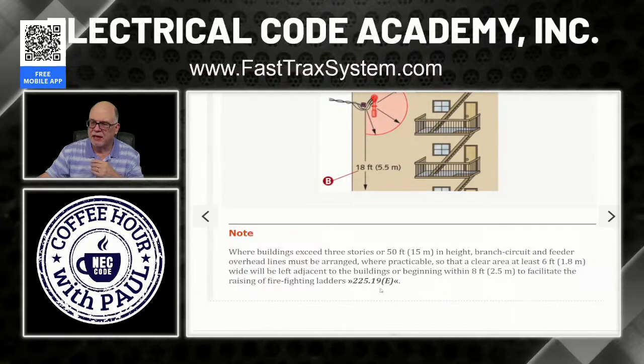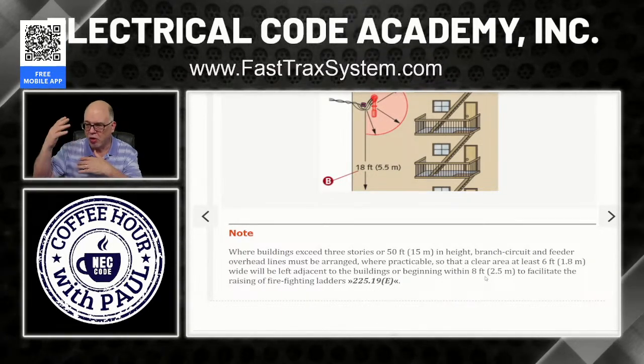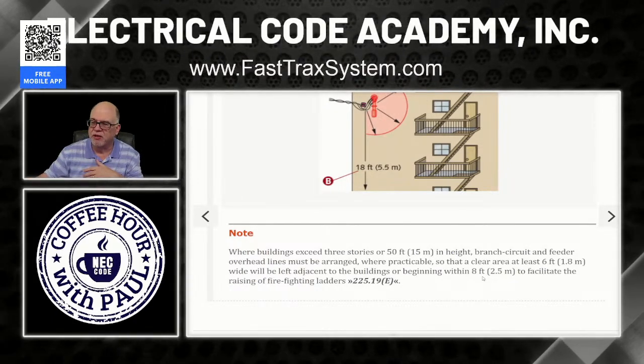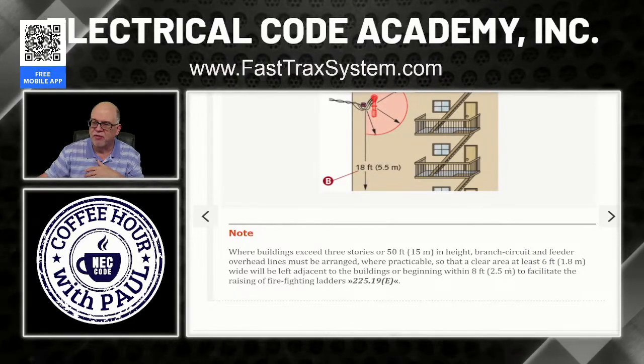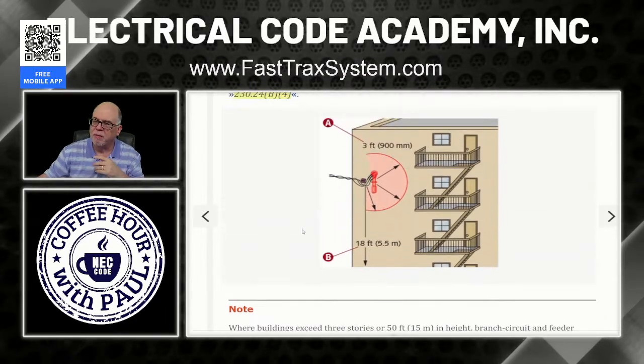Where does it begin? It begins at 8 feet, right? And again, it goes up to the 50 feet or higher if it exceeds three stories or 50 feet. And so the clearance area is 6 feet wide. So you have to make sure you have that clearance there. All right, but let's talk about this here real quick.